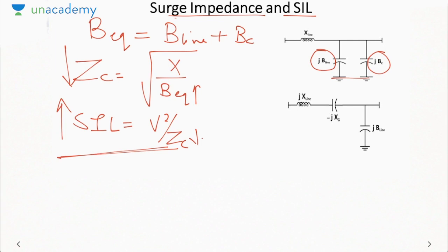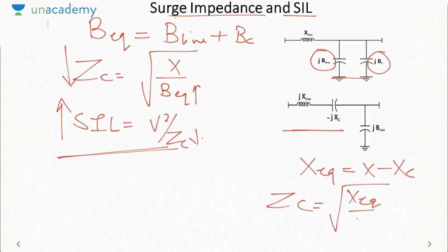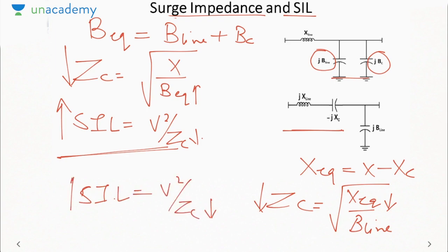So by the use of shunt capacitor, surge impedance loading increases, which is an advantage as the transfer capacity of the line increases. Next, let us see series capacitor. Here X equivalent becomes X minus XC. So ZC will be under root X equivalent by B line. Since X equivalent reduces, ZC reduces. And SIL, which is V square by ZC, increases. So here also surge impedance loading increases as we use series compensation. So by using the capacitor whether in shunt or series, the surge impedance loading will always increase. Okay, that is, the power transfer capability of the line will always increase.